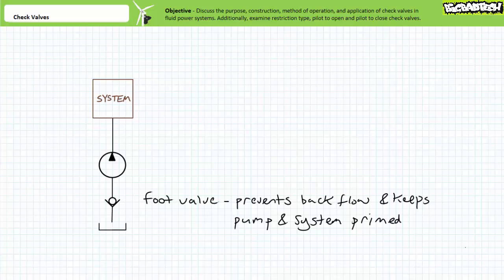Consider a check valve located on the intake of a pump. In such an application, this check valve might be known as a foot valve. This check valve's orientation allows liquid to be sucked up by the pump. However, when the pump stops pumping, it prohibits any liquid in the system from draining out. The foot valve therefore prevents backflow and keeps the pump and system primed and filled with fluid.